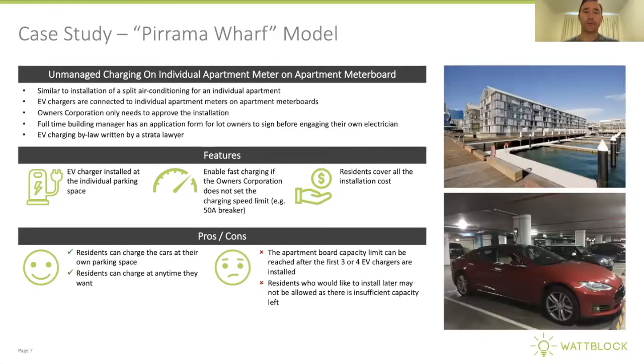At Pirrama Wharf in Pyrmont, we have an example of unmanaged charging on an individual apartment meter board — a meter board that only has apartment meters on it. A new 50-amp breaker was installed, and the Tesla charge station was put on a pylon near the car. This was with approval of the strata committee, and the building and facilities manager put in place a document to be signed off by each resident wanting to install an EV charging station, including the owner being responsible for checking the RCDs on a periodic basis if required by law.